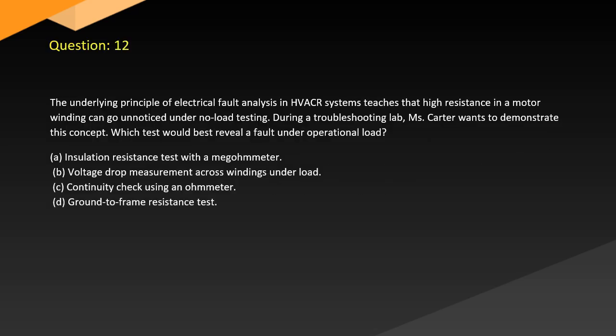Question 12. The underlying principle of electrical fault analysis in HVACR systems teaches that high resistance in a motor winding can go unnoticed under no-load testing. During a troubleshooting lab, Carter wants to demonstrate this concept. Which test would best reveal a fault under operational load?